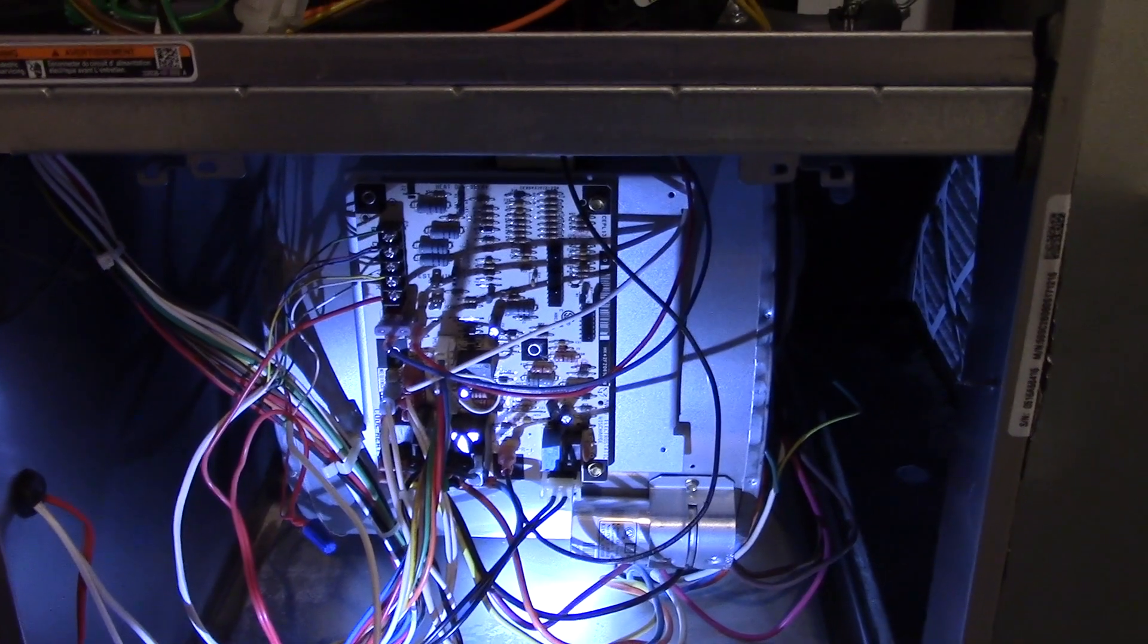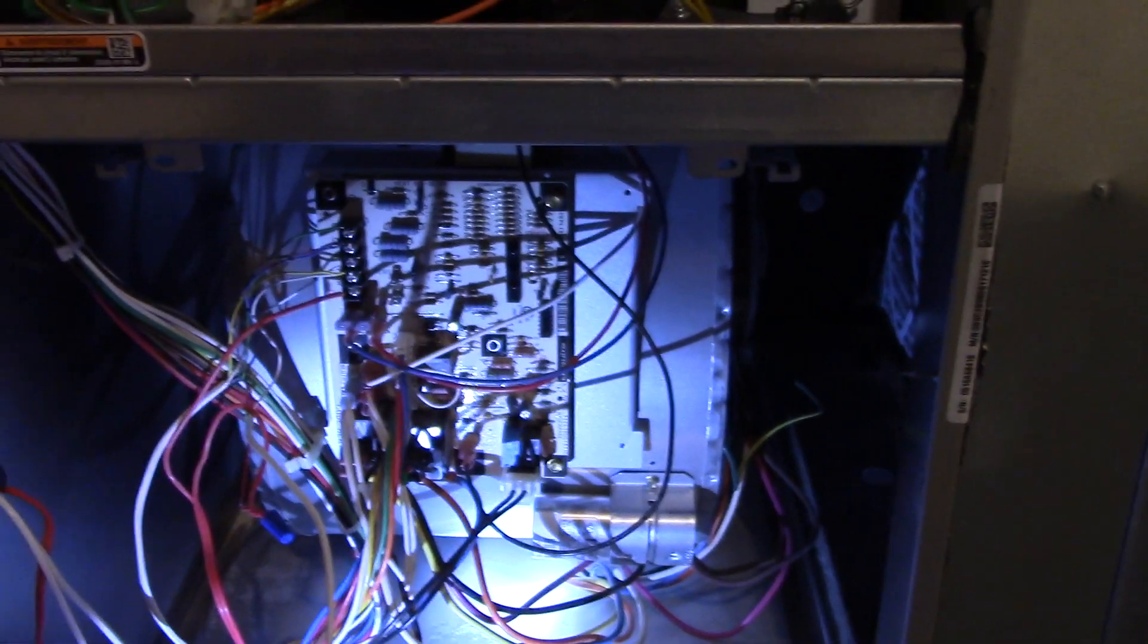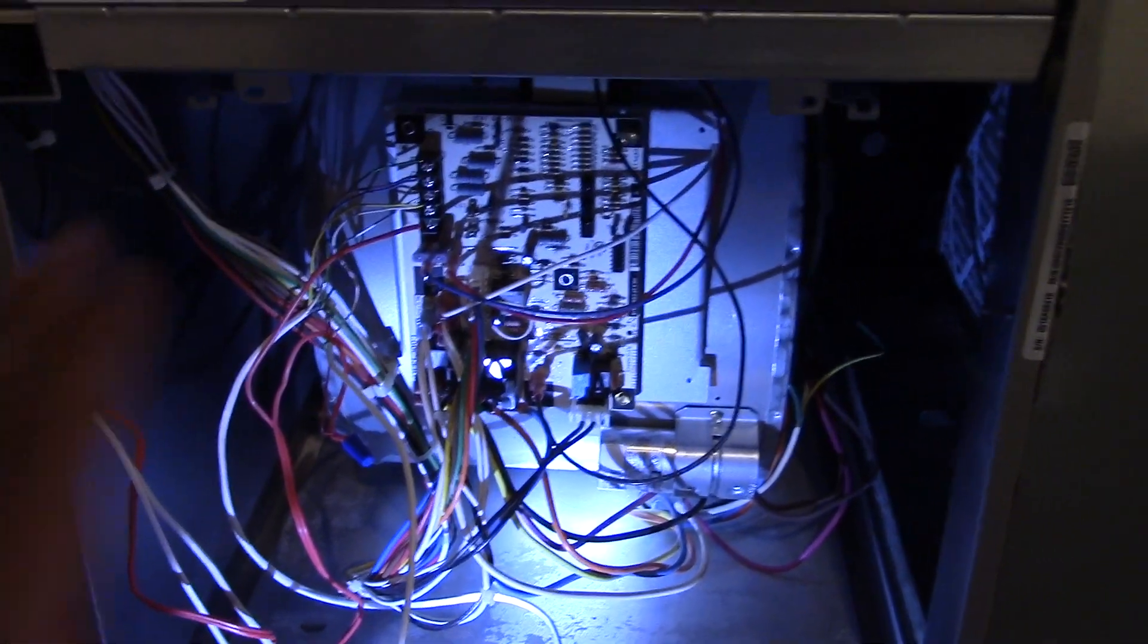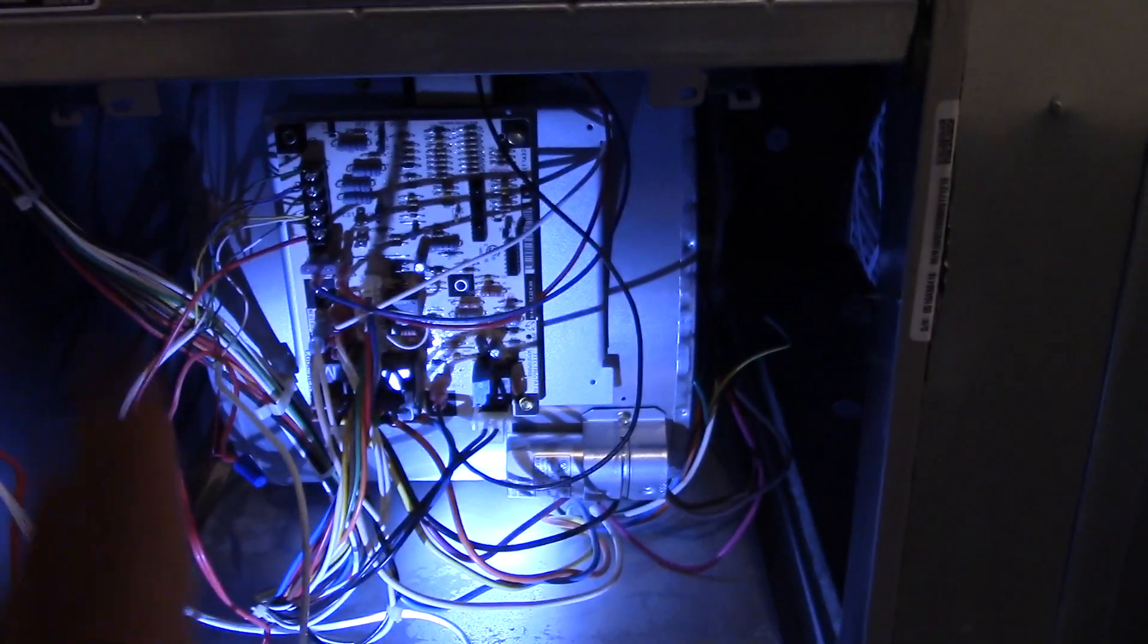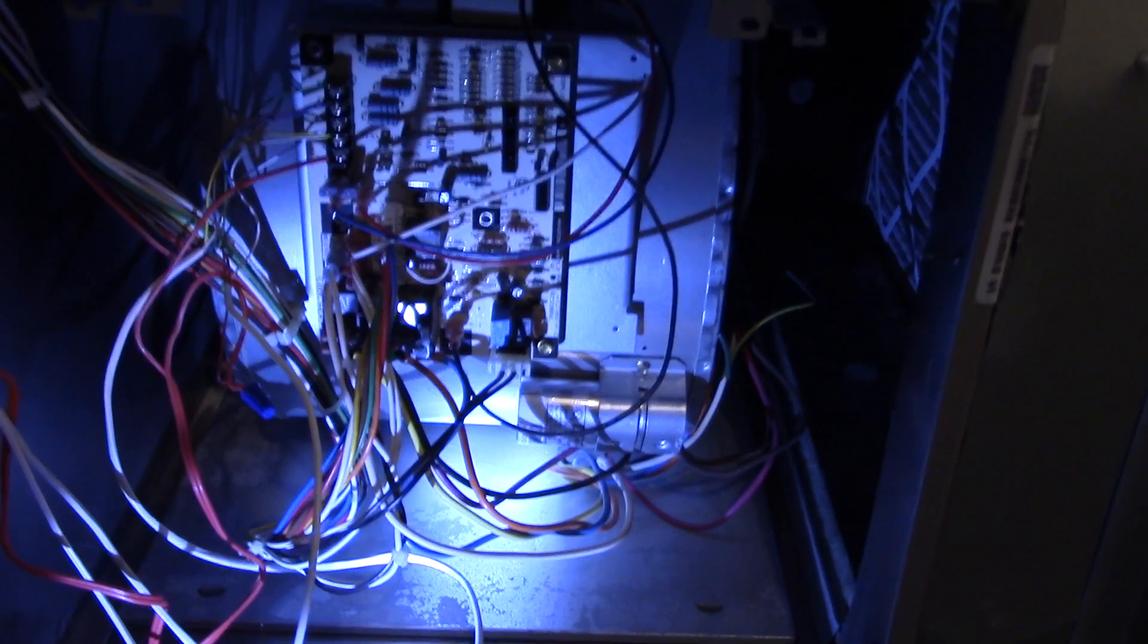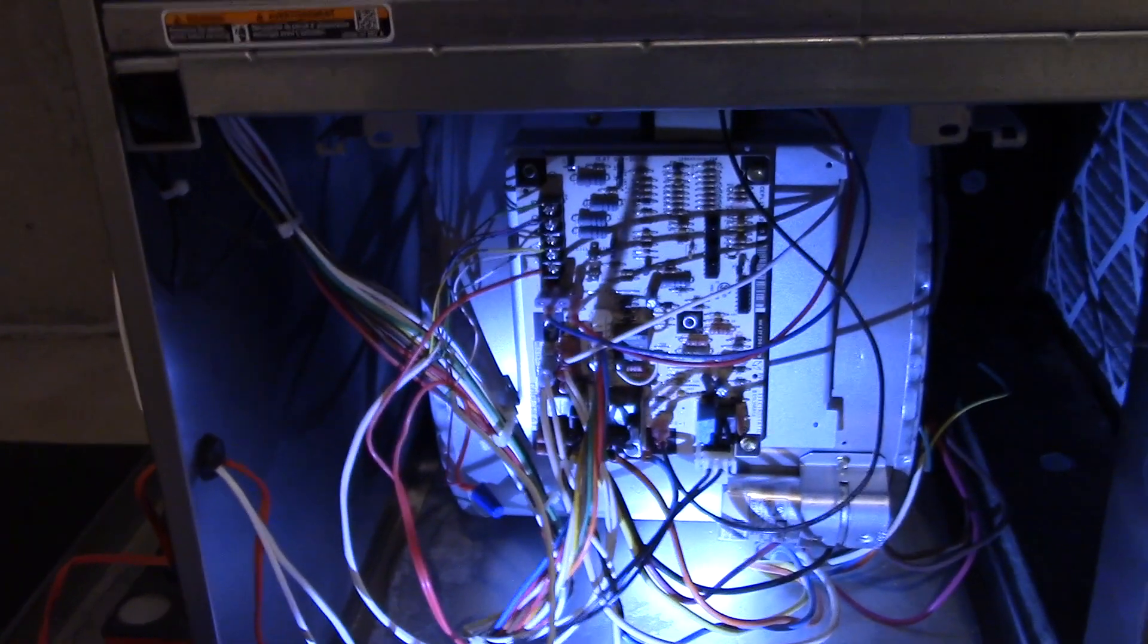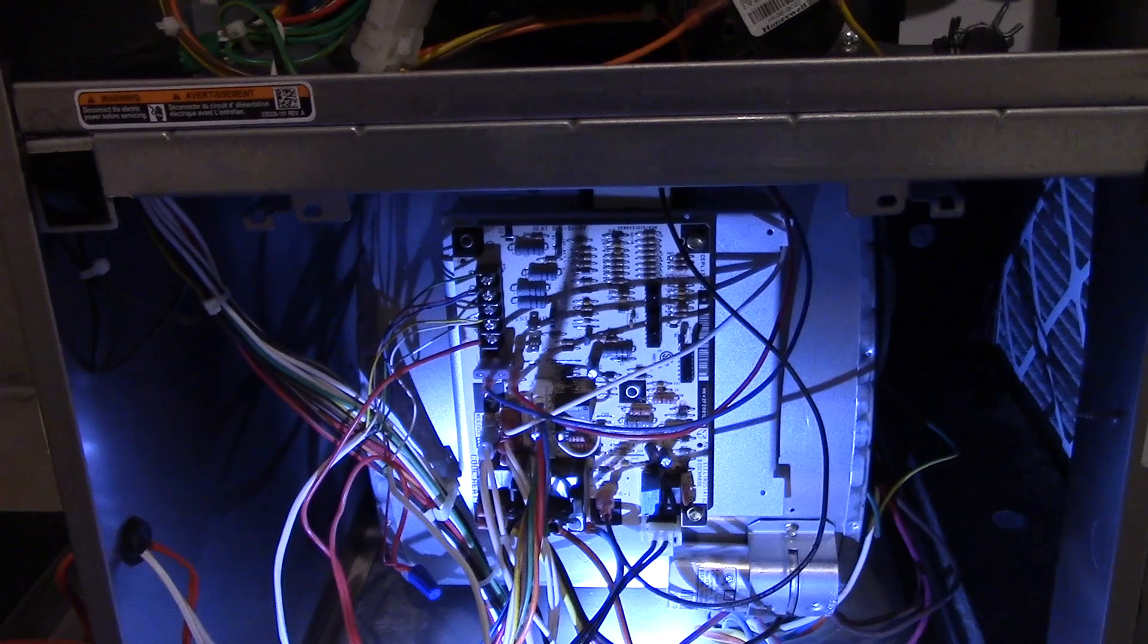And basically guys, that's how you figure out your blower speeds and how you possibly adjust them for heating speeds. Again, I do not recommend slowing down your cooling speed. Generally, raising your heat speed should be okay. Again, if you attempt to do this, please be safe. When you're messing with anything on the board, be absolutely sure the power is off and be very careful handling anything inside here. And when you do this audio test and you're holding down on the switch, don't put your hands anywhere in here and keep everything all clear of the blower. So that's basically your furnace speeds. It will be different for brand to brand, but generally the board should have a similar labeling on it so you can tell what it is going to be for what speed and similar to this video.